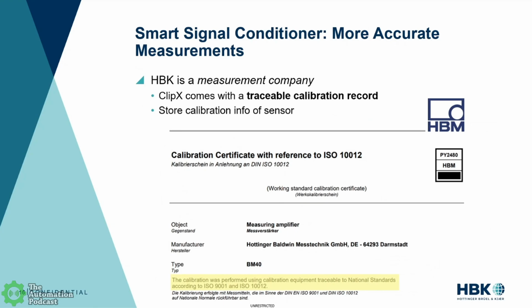The nice part about being a digital device is that if you have a digital calibration record for the sensor plugged into this ClipX, you can store that on the ClipX too, which makes keeping all this information straight a lot simpler. This is very important in case of an ISO 9001 audit, or in case of a recall—you need to be able to prove that these instruments have a traceable calibration.